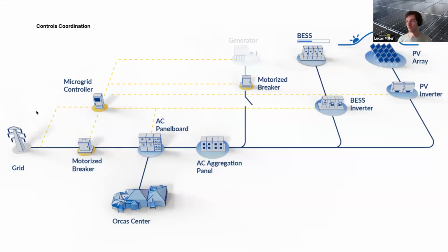Just to give us a lay of the land, what we're looking at here is a very overly simplified block diagram of this microgrid. Starting from the left, we have our grid interconnection tied in via motorized breaker to our AC panel board within the Orcas Center facility. Underground trenching to an AC aggregation panel that's co-located with everything you see over here. So a motorized breaker to connect and disconnect our generator, our BESS and BESS inverter, our PV array and PV inverter. Our first viewpoint here, we're calling this the morning.